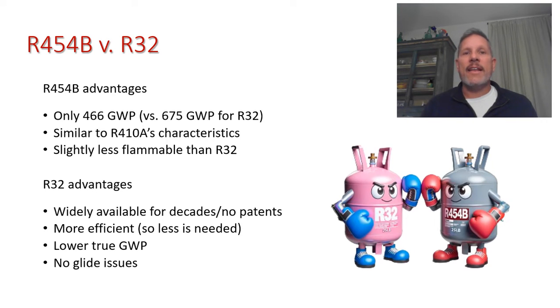A lot of manufacturers are saying they don't want to keep changing their refrigerant every couple of years, so they're committing to R454B, expecting it to be good even if the EPA lowers the cap to 500. Additionally, R454B isn't exactly a drop-in for R410A, but it has similar efficiency and pressure, making it less work to adapt current machines to run with R454B.